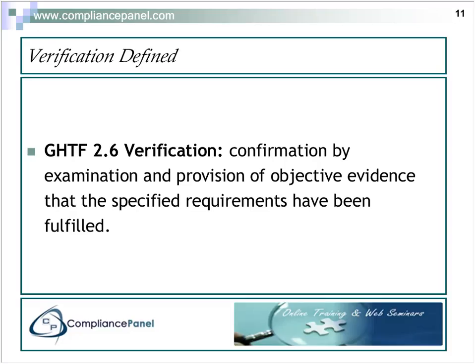But verification is also an inspection activity that may take place during the production of our product, and that could be at incoming, in process, or final inspection. It's also a verification activity that may take place during our process validation. In other words, we're following this particular protocol, and we're verifying that that protocol was executed successfully. So we'll provide this objective evidence that this protocol has been actively and successfully completed.